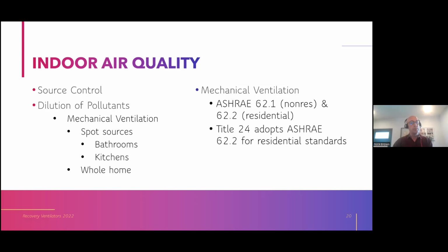And then the second step is dilution of the pollutants, because pollutants are going to be present in our buildings. Mechanical ventilation is constantly bringing in outdoor air, assumed to be fresher and less polluted, and diluting what's happening inside with it. Because whenever we cook, whenever we shower, we're creating moisture, and excessive moisture is one pollutant that can lead to problems in our indoor spaces. We're creating VOCs when we cook, right? Maybe we just bought furniture from IKEA, or well, IKEA is a bad example because honestly, they're pretty good environmental stewards. But a new foam mattress, let's say, that's going to create indoor pollutants that need to be vented out. Our furniture, our rugs, all these things are contributing, and so that's why we need mechanical ventilation in today's spaces, especially given the fact that we're building our buildings tighter than ever, right? And we're spending more time than ever in them.